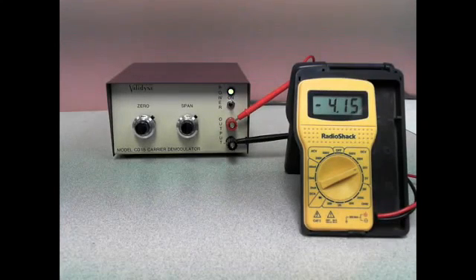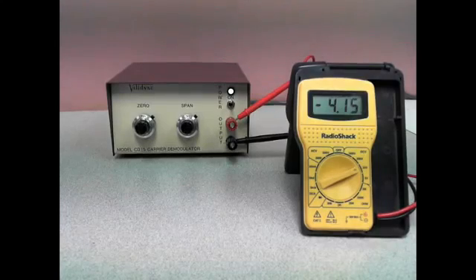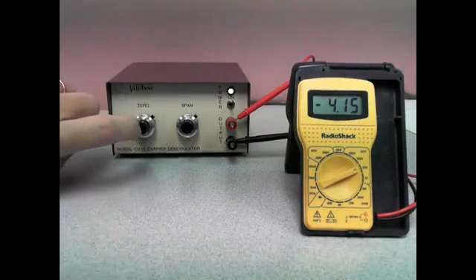Tap the zero and span adjustment knobs to see if the signal jumps. This could indicate a worn potentiometer.